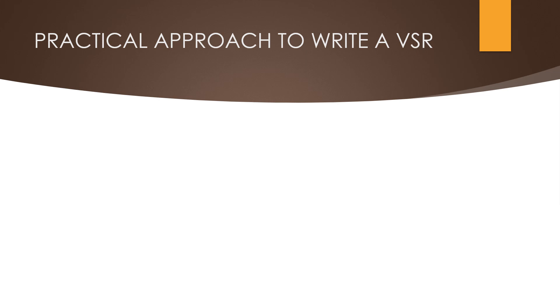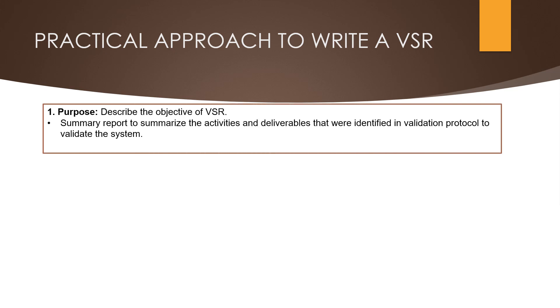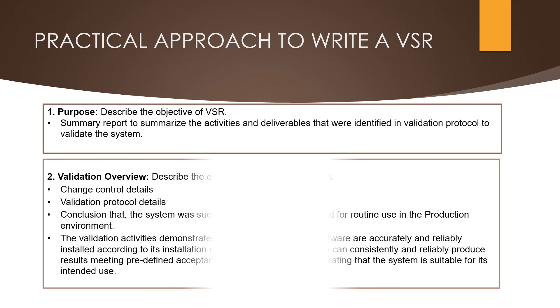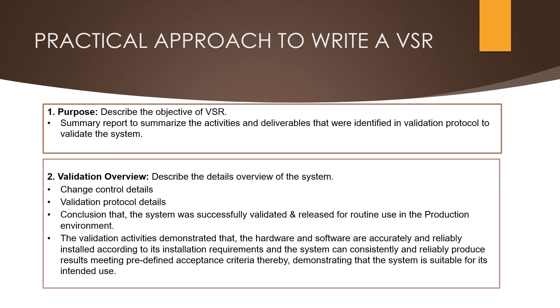Now we will discuss the practical approach to write a validation summary report. The first component is the purpose section, which defines the objectives of the overall validation approach. In the purpose section, we need to define the objective such as: this validation summary report is to summarize the activities and deliverables that were identified in the validation protocol to validate the system.